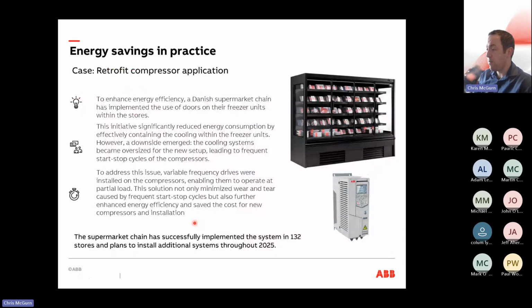Another case study here was for a Danish company. They recently changed their refrigeration cabinets so that they implemented the use of doors on their freezer units. Now, this significantly improved their energy consumption by containing the coolant within the freezer units. However, because of that, the coolant systems were actually oversized for the new setup, and it meant that the compressors were start-stopping all the time.